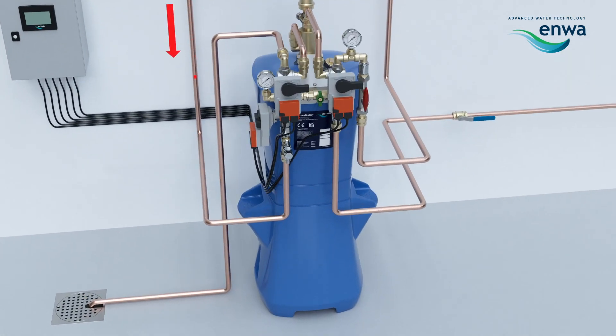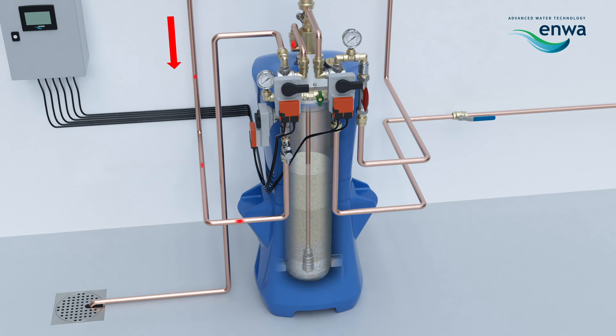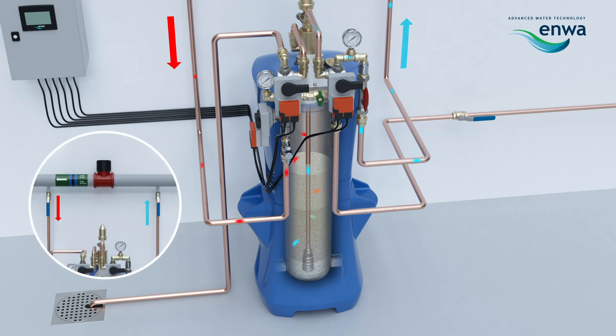The untreated water from the system enters the Enwamatic. The water is filtered and treated as it travels down the layers of filtration and treatment media. The cleaned and treated water exits through the strainer at the base of the unit and travels upwards through the central pipe. The side-stream loop is driven by the differential pressure across the circulation pump.